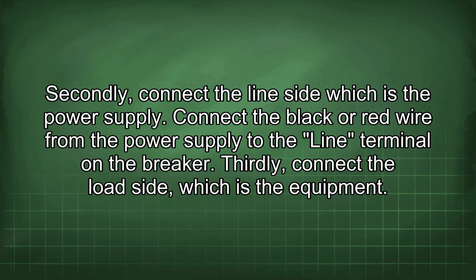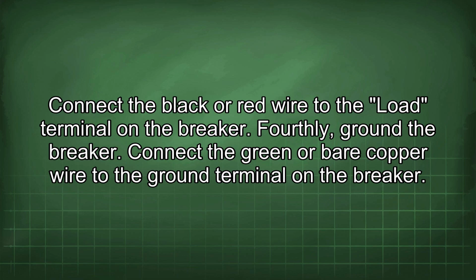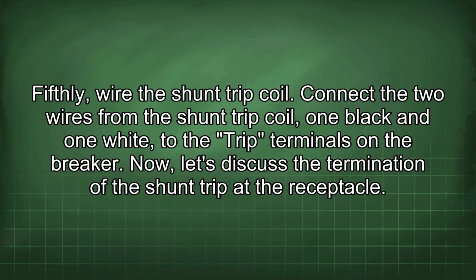Thirdly, connect the load side, which is the equipment. Connect the black or red wire to the load terminal on the breaker. Fourthly, ground the breaker. Connect the green or bare copper wire to the ground terminal on the breaker. Fifthly, wire the shunt trip coil. Connect the two wires from the shunt trip coil, one black and one white, to the trip terminals on the breaker. Now let's discuss the termination of the shunt trip at the receptacle.